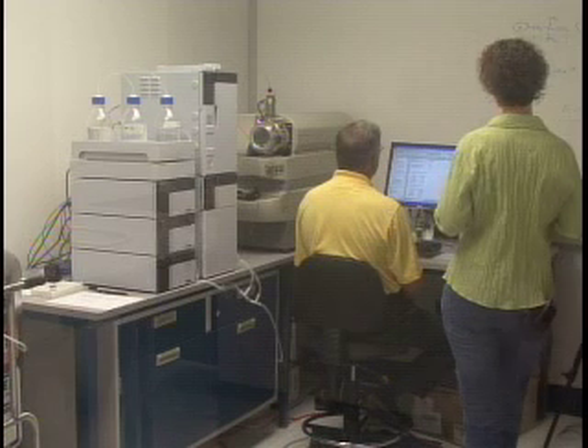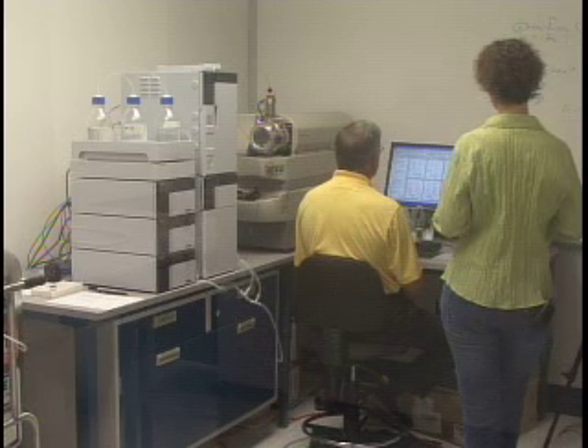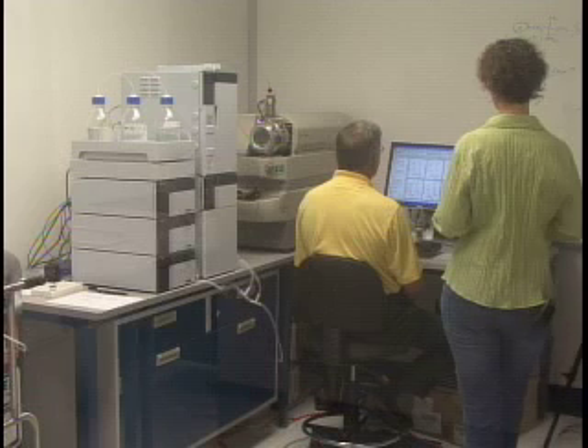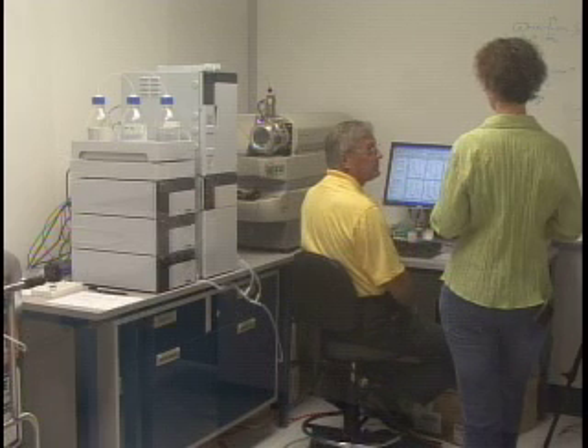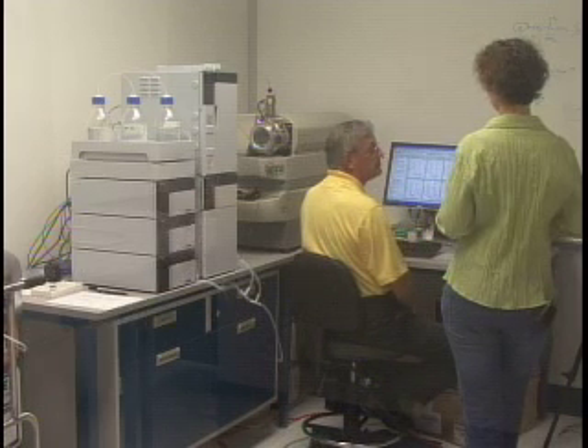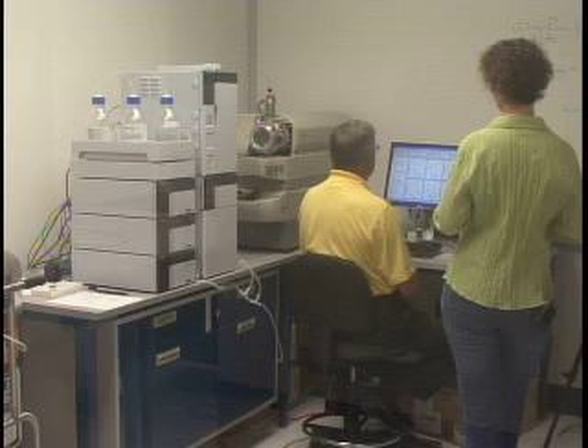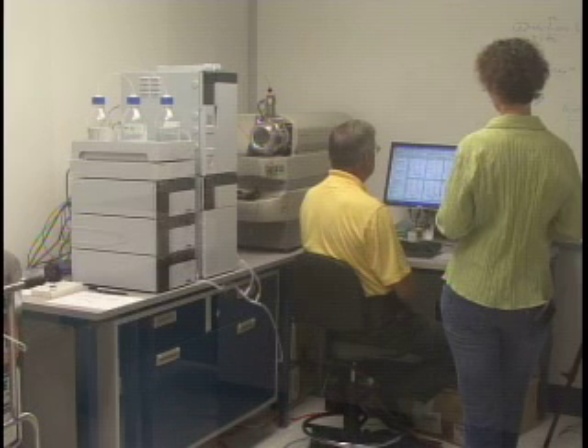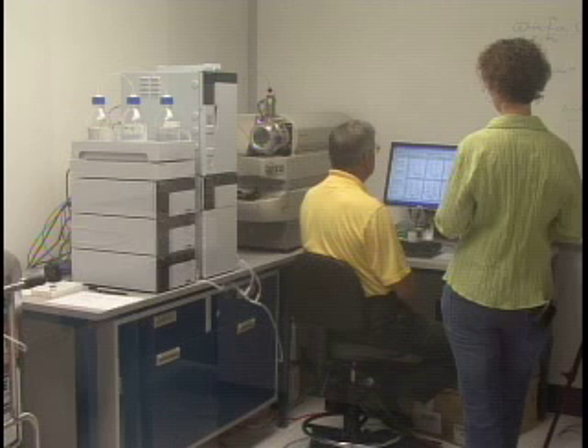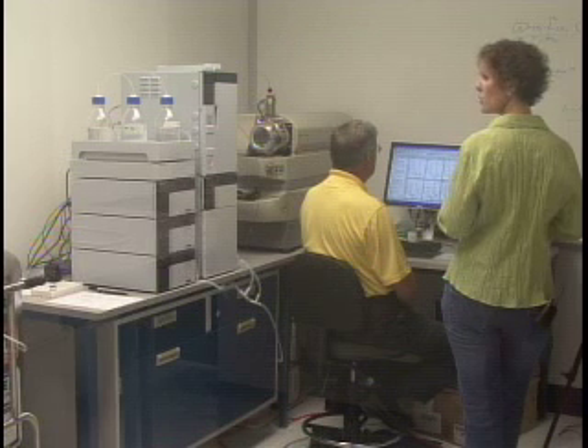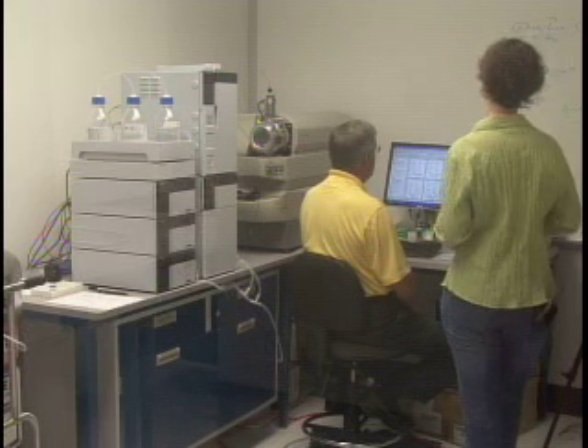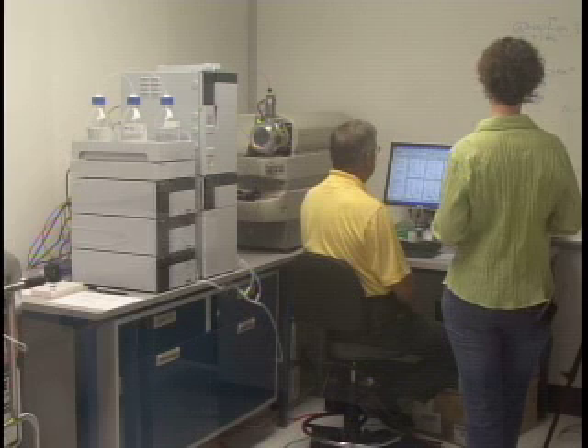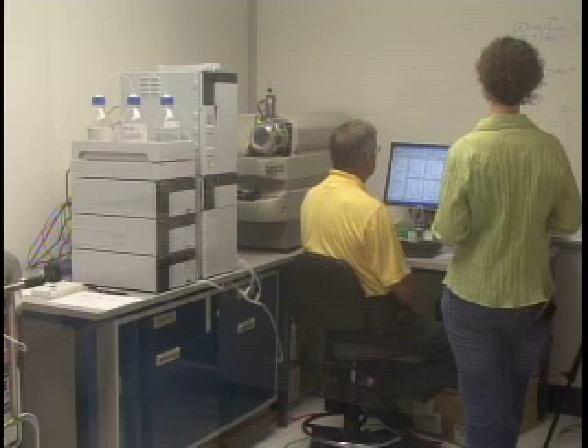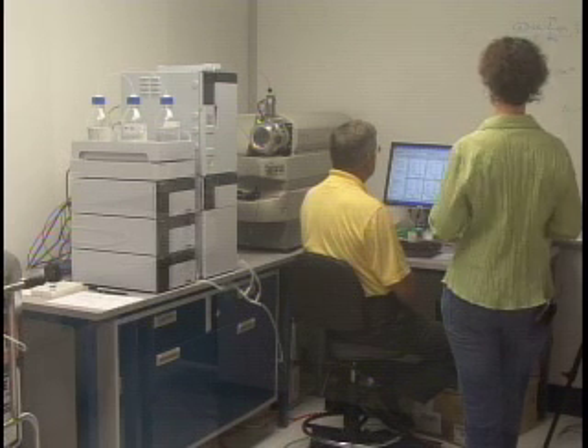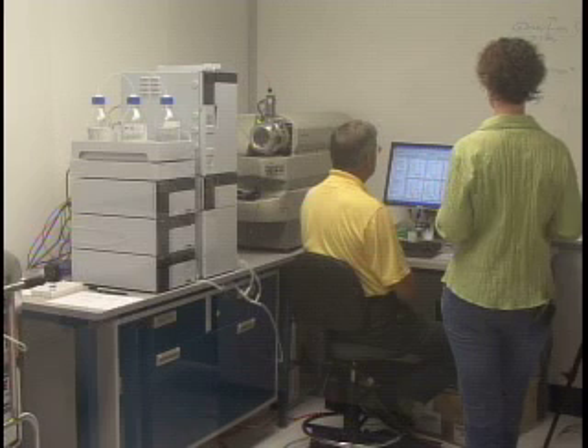So the one thing we don't have to change when we do this is there's no place for it to ask you what speed you want the syringe pump to be running. So whatever speed the syringe pump was running in the manual tune check mode is the speed it's going to use for the resolution optimization. Good point. So normally we do this function at 10 microliters per minute because that's the same speed we use in the checks.